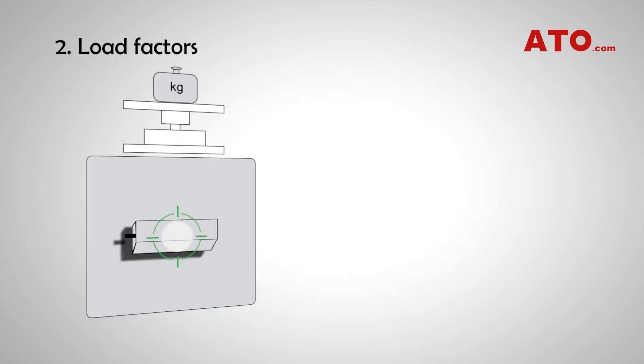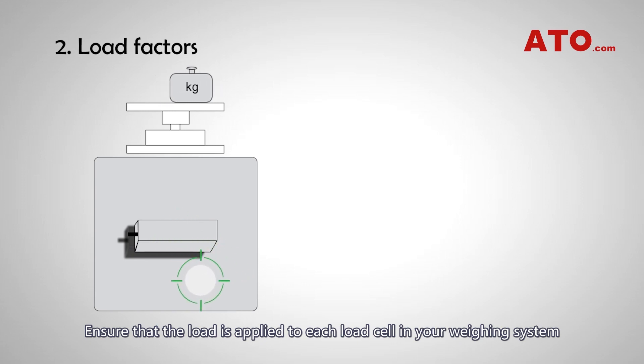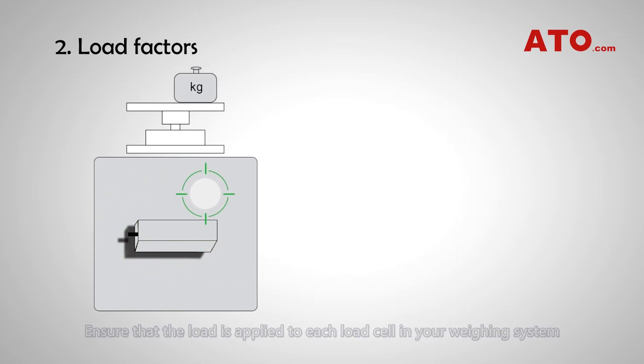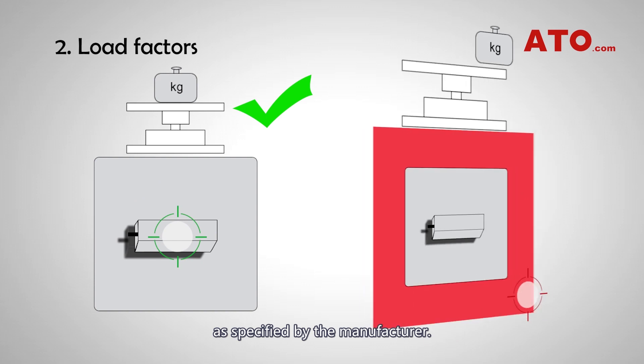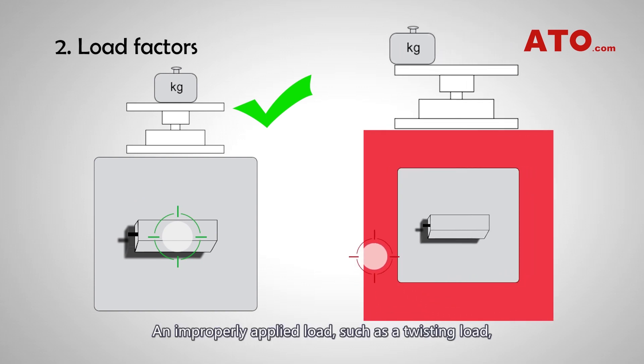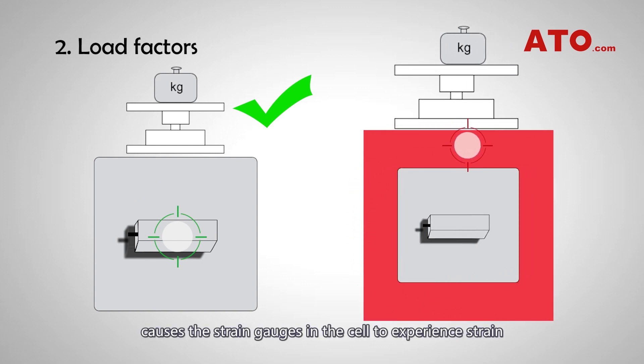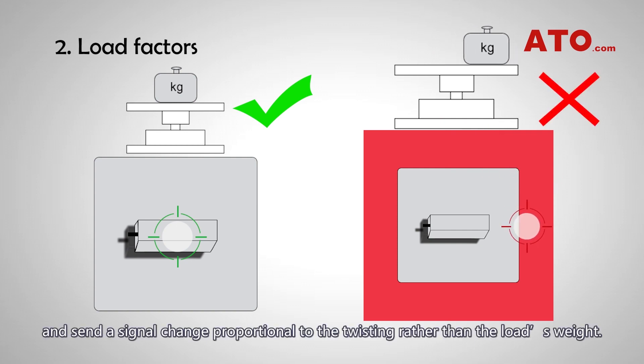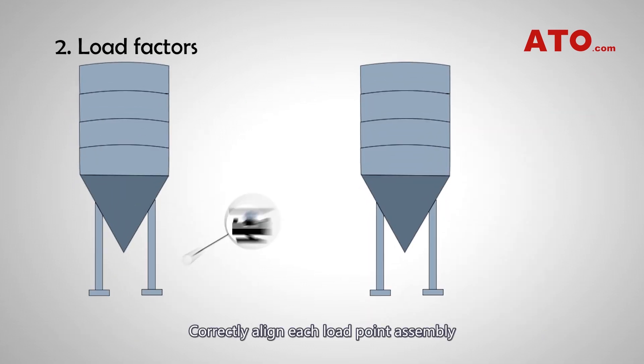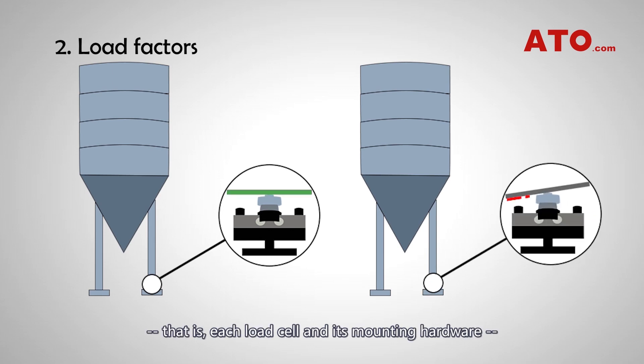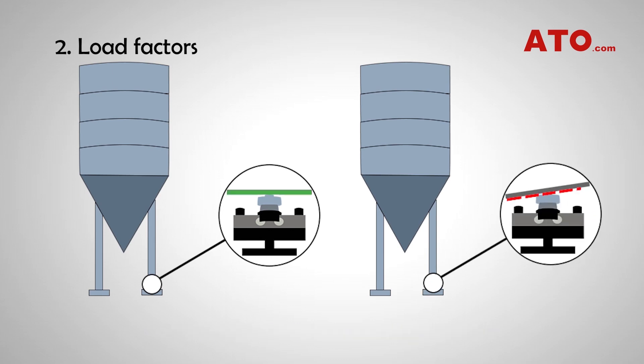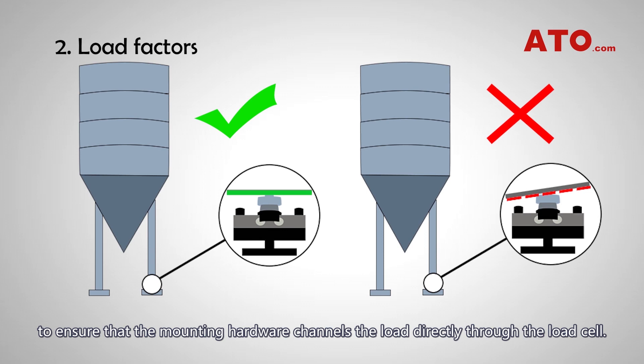Load factors. Ensure that the load is applied to each load cell in your weighing system as specified by the manufacturer. An improperly applied load, such as a twisting load, causes the strain gauges in the cell to experience strain and send a signal change proportional to the twisting rather than the load's weight. Correctly align each load point assembly — that is, each load cell and its mounting hardware — to ensure that the mounting hardware channels the load directly through the load cell.